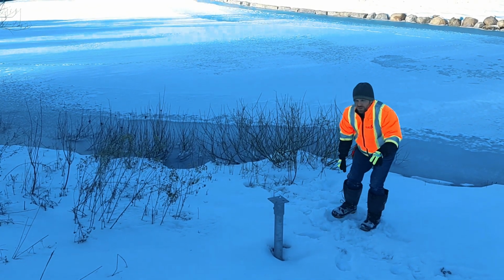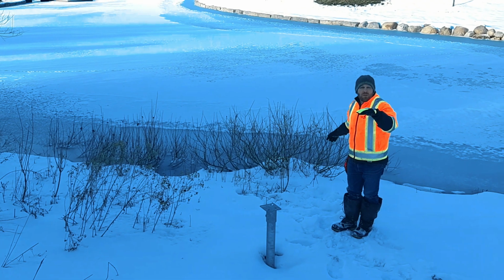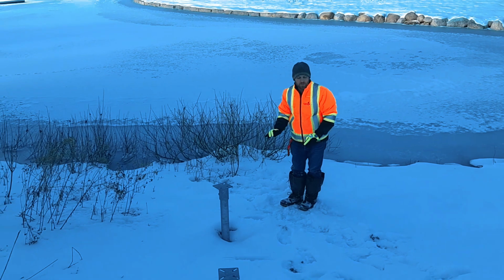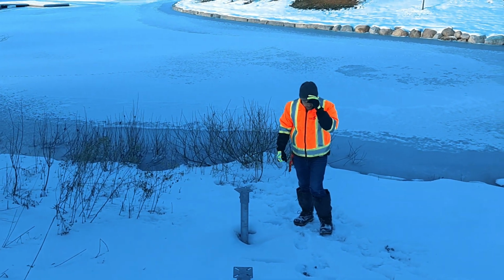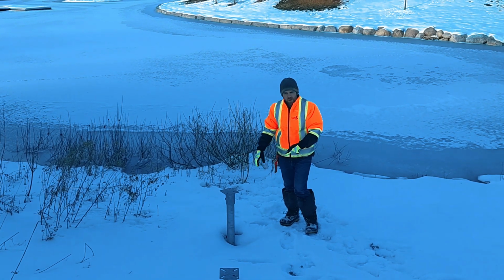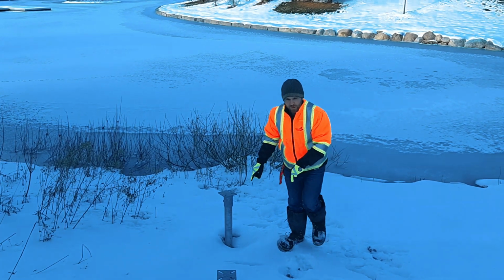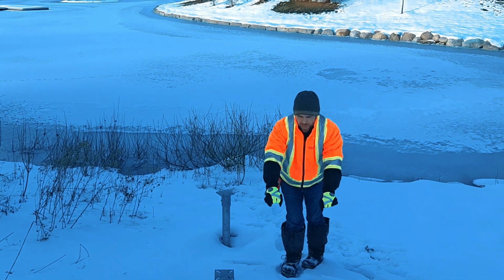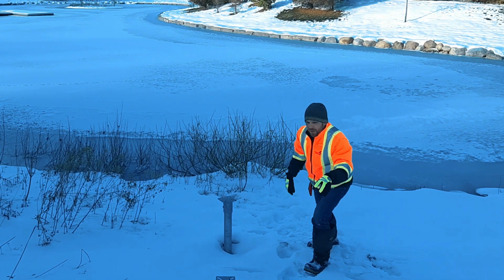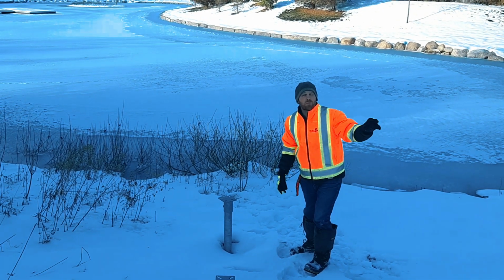Gotcha. The pump's designed to be able to prime without a check valve at 9 feet above water level. Okay. But it just puts a lot more work on the pump, right? So this way this thing will prime nicely. Yep. And I was worried that you're going to make it try to prime without the check valve, but it won't really be the case because you're going to turn the pumps off, close these gate valves, and switch that out with no check valve, right? Then you're going to open these gate valves and the whole thing will be flushed full, and you'll turn the pumps back on and it'll prime right up.